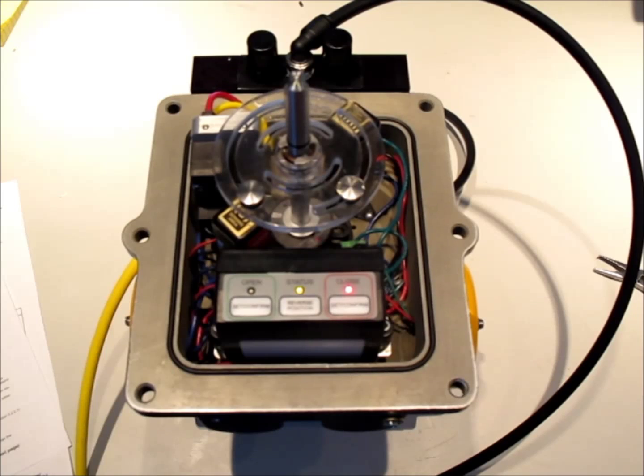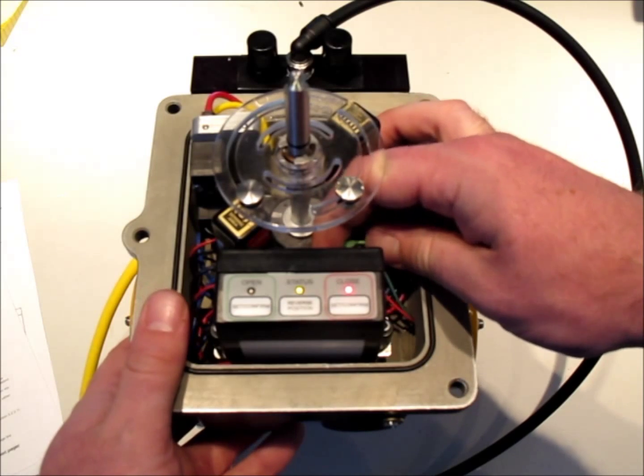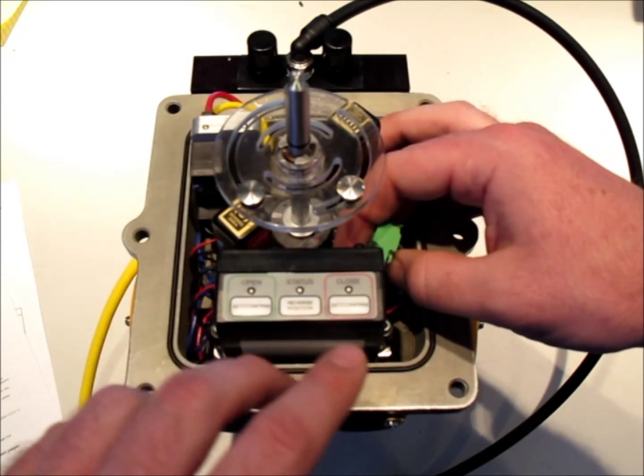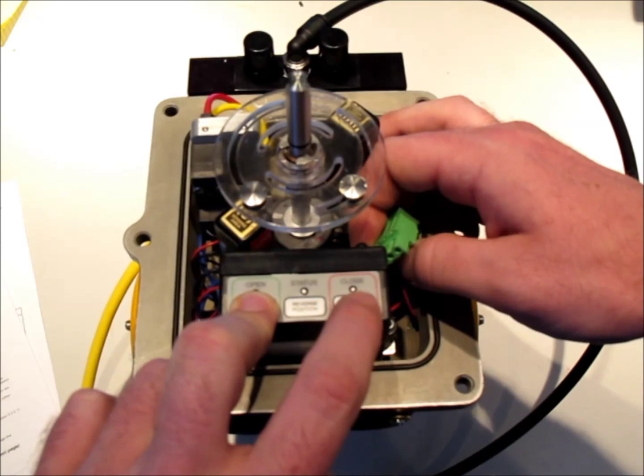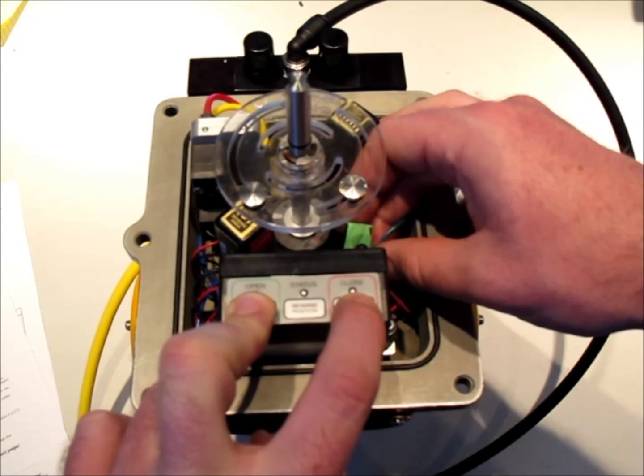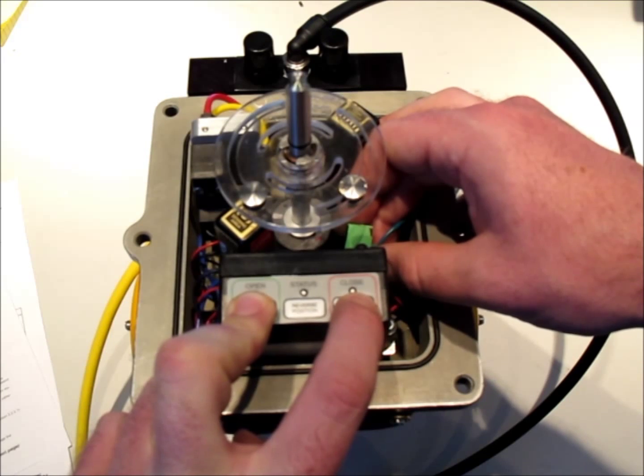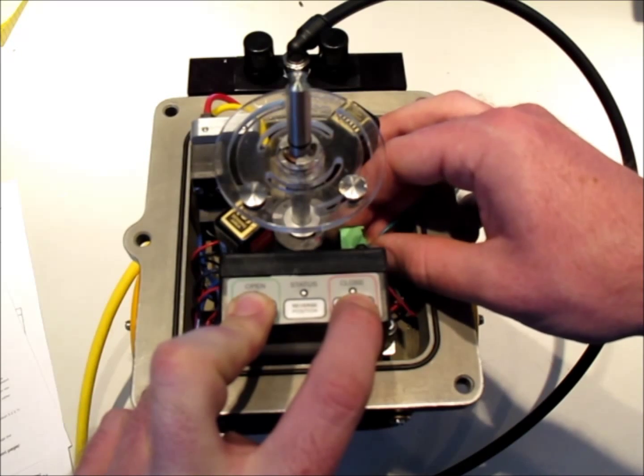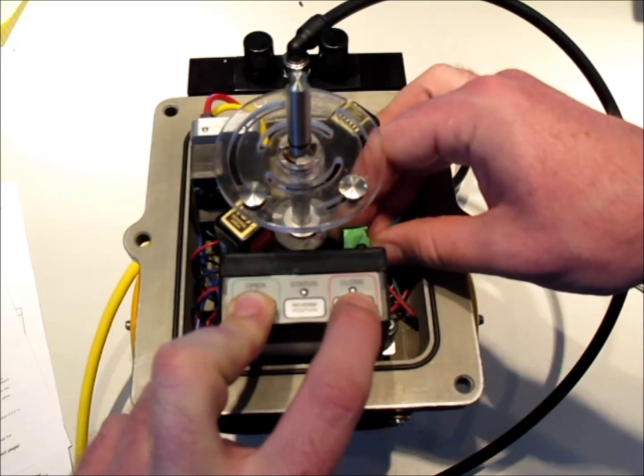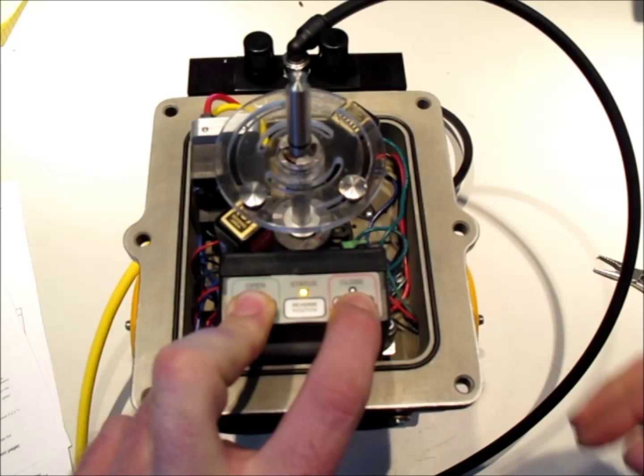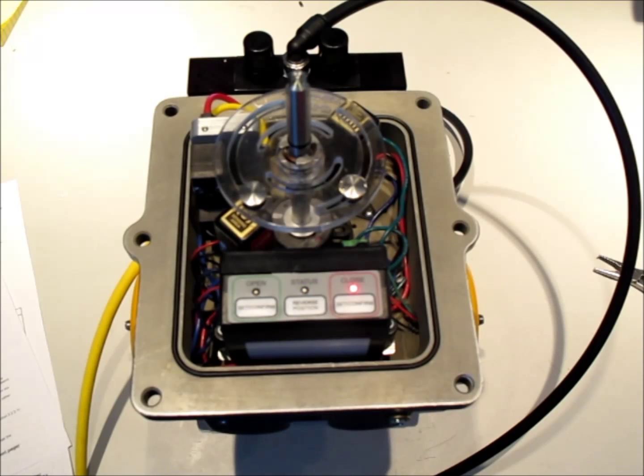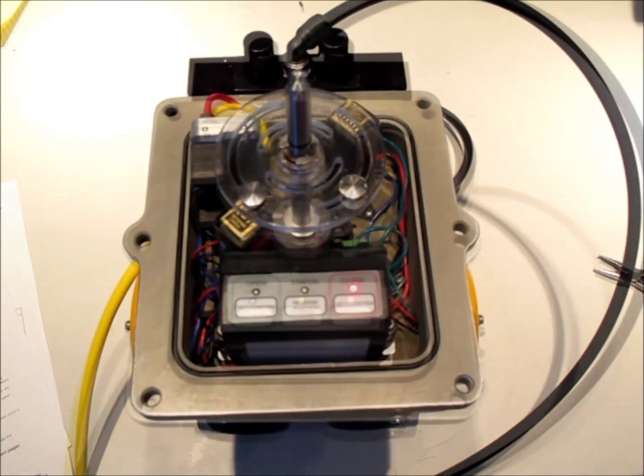To restore factory defaults locally, remove power from the cube. Now, before restoring power to the cube, press and hold the Set and Confirm buttons for both the open and closed side, and then release once powering up. Now you can confirm that you've restored to factory defaults as the status light is now flashing, indicating that a calibration is needed.